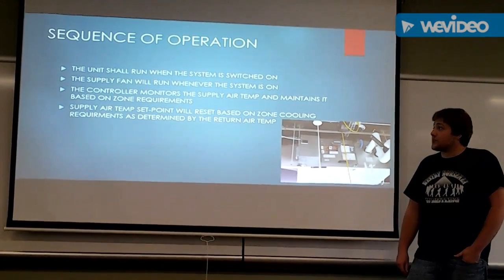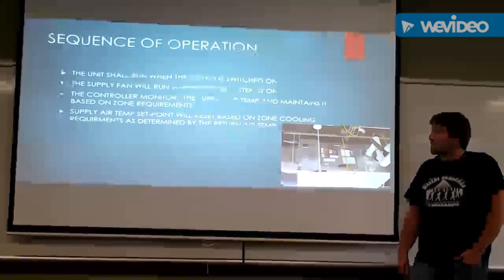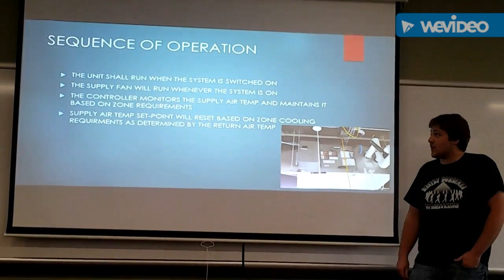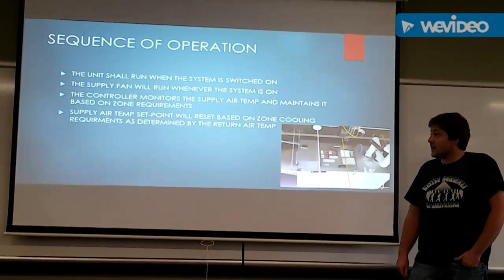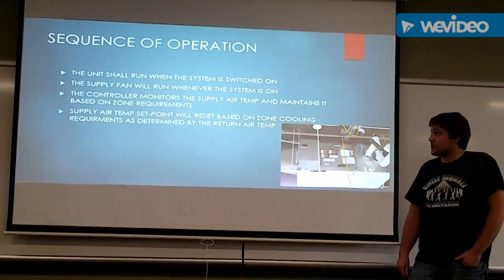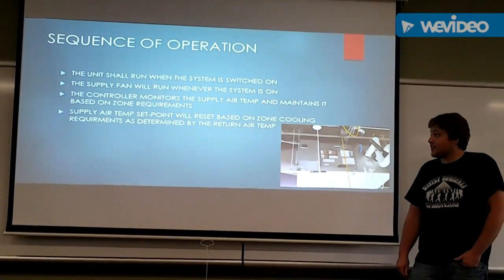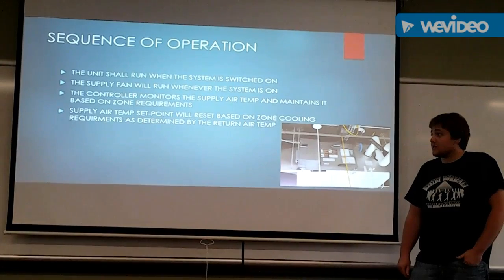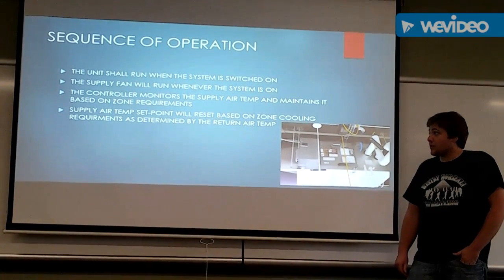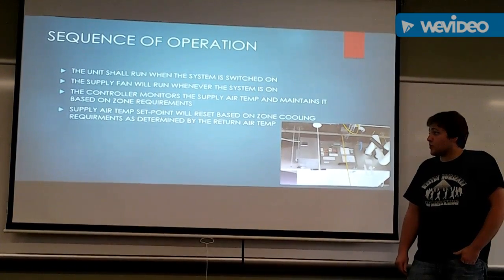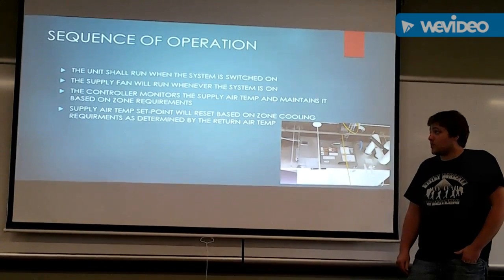Sequence of operation. The unit shall run when the system is switched on. The supply fan will run whenever the system is on. The controller monitors the supply air temp and maintains it based on the zone requirements. Supply air temp set point will be reset based on the zone cooling requirements as determined by the return air temp.